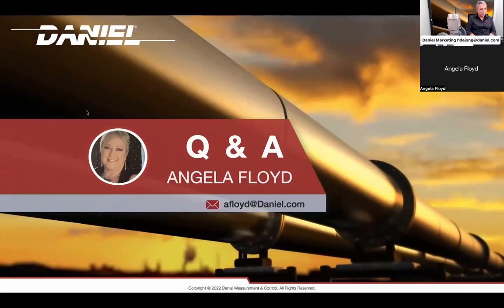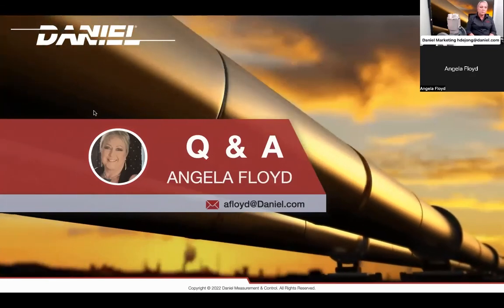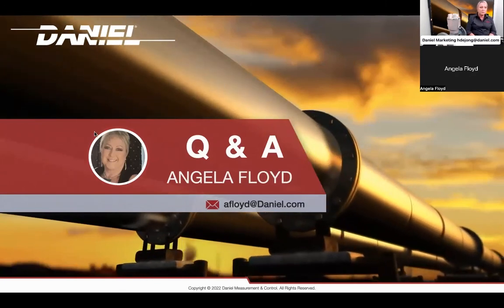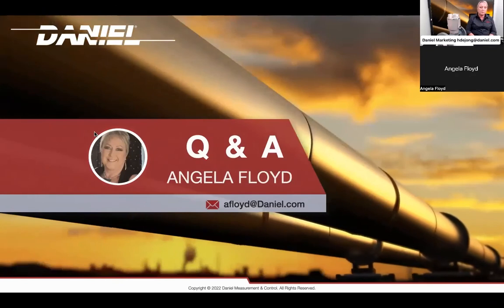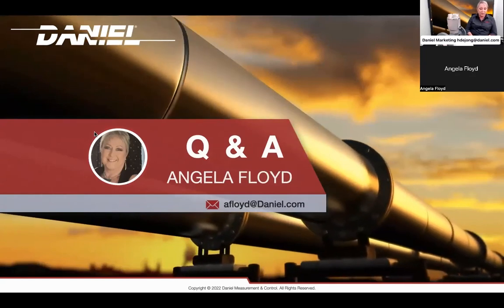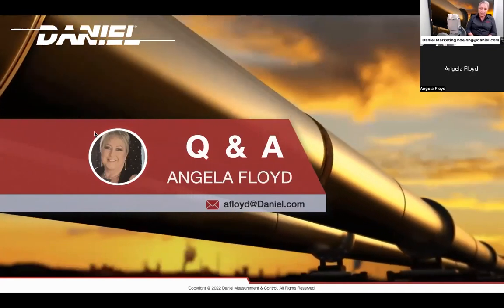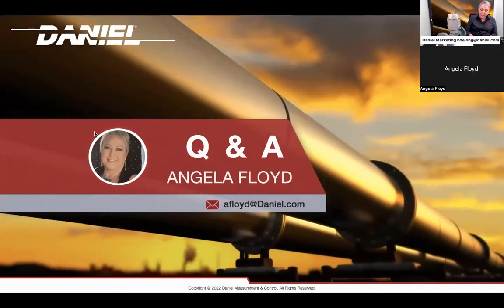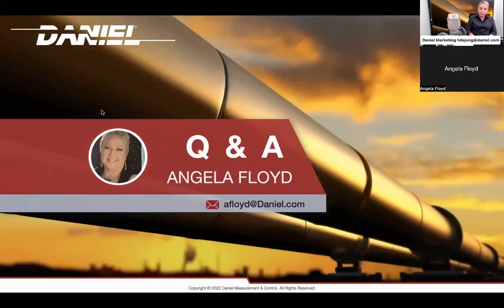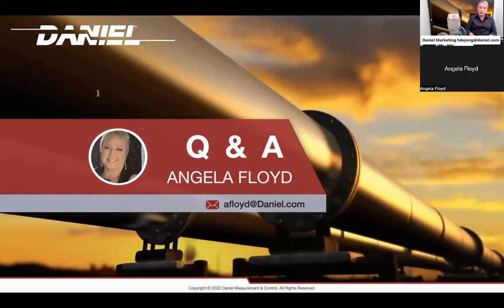Another question: small turbines should usually be calibrated with the specific kinematic viscosity of the fluid they'll work with. Are your turbines calibrated to the specific properties of the fluid? How do you assure the performance of the turbine if the pipe handles different types of fluids? Our facility in Chihuahua calibrates on mineral spirits. If you require calibration in your own product, we would use a third-party calibration facility and have it calibrated at your flowing conditions across the full range of your requirements — it's not something we do internally, but we have the relationships with third-party labs to do that.